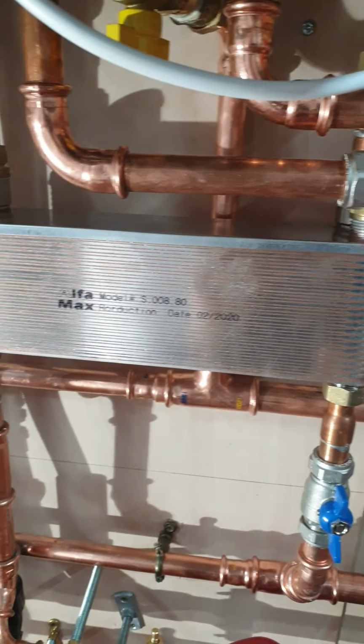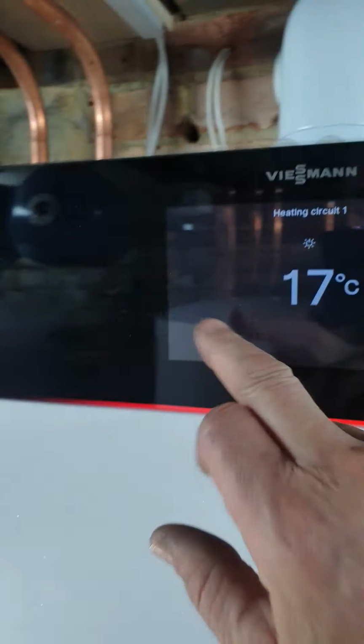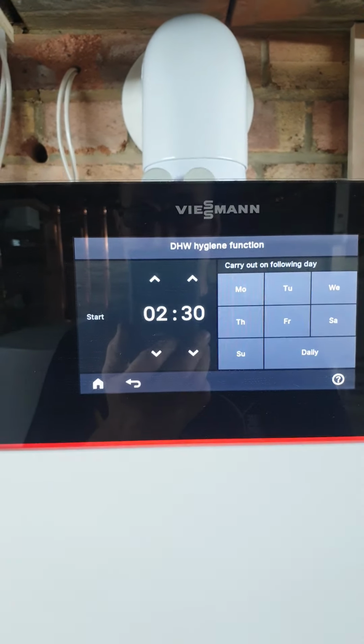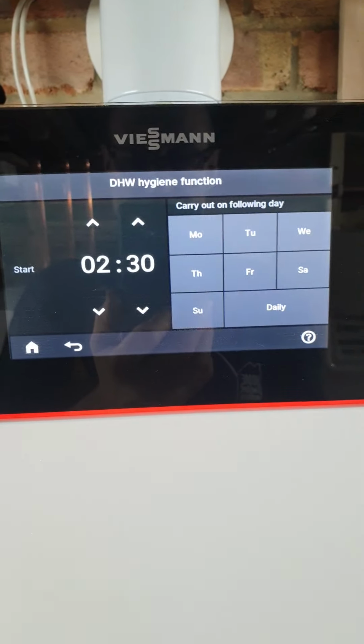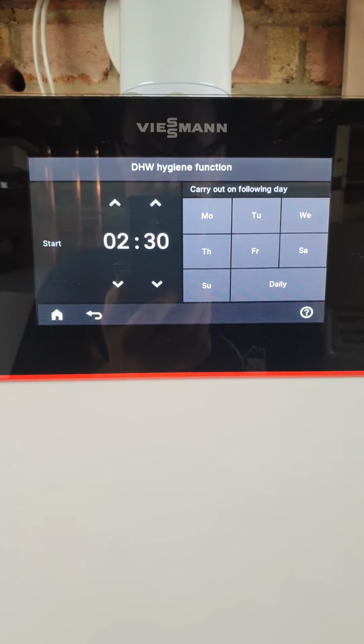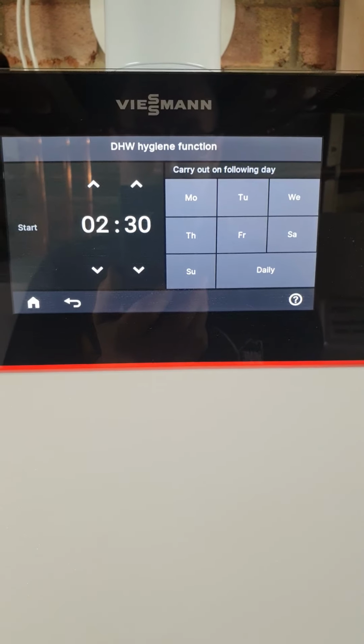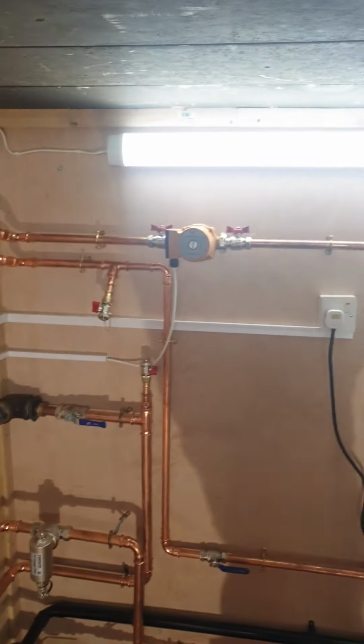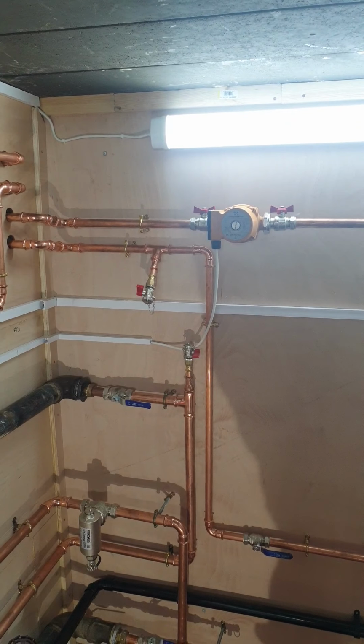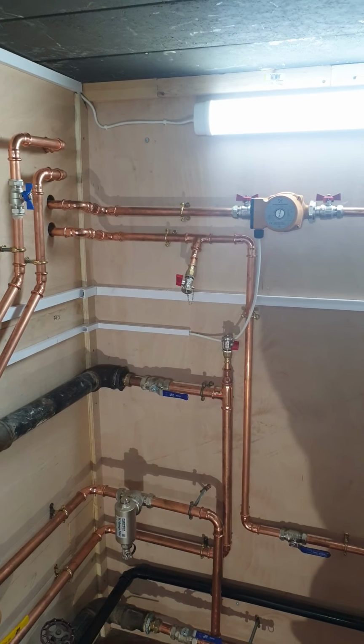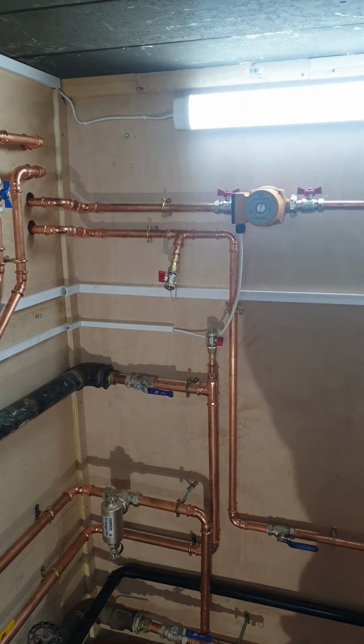And that's it. Now this has got new functions in the controller. The new controller here, we have in the hot water function, here we have the hygiene function, which we've set daily. So this is going to be the Legionella function at 2:30 daily, and that runs the bronze circulation pump there and ramps the hot water temperature up really high and cooks all the pipe work and the cylinders to kill off any bacteria and germs. And that's that one.